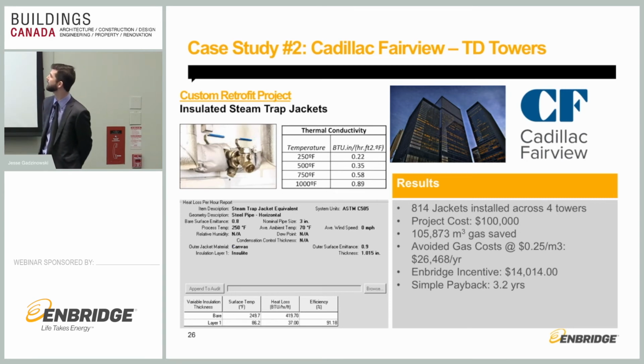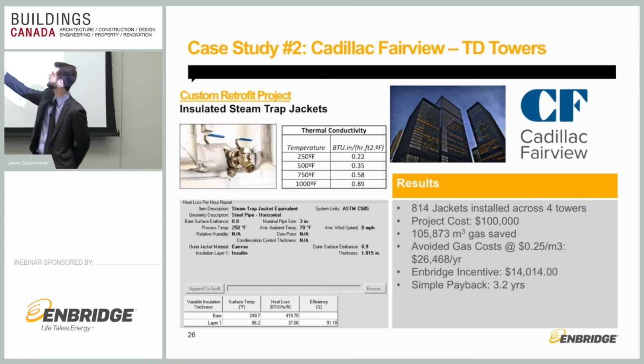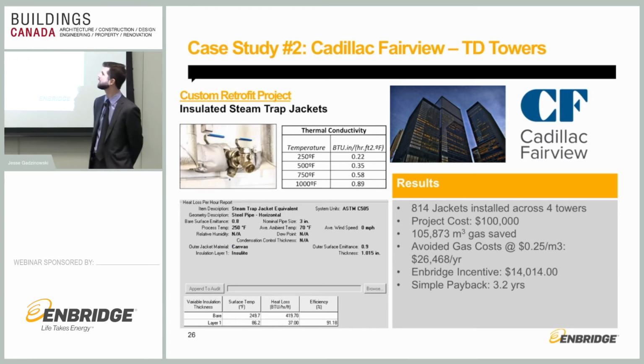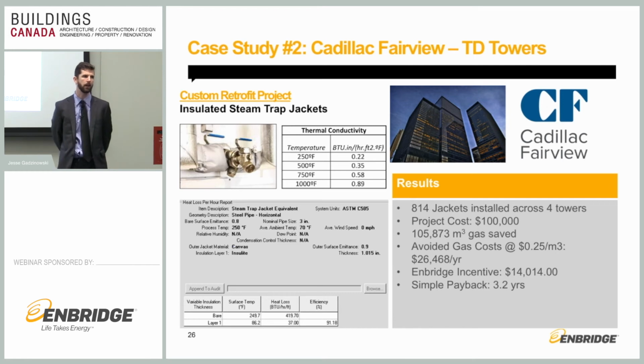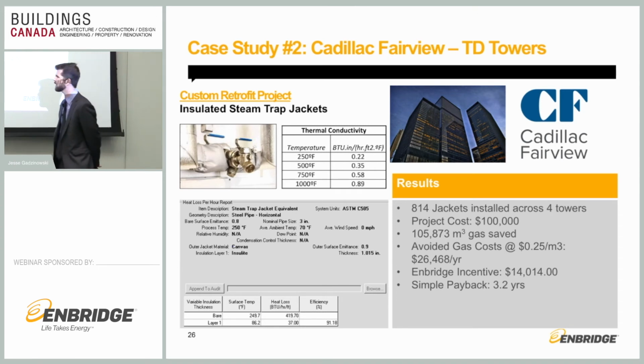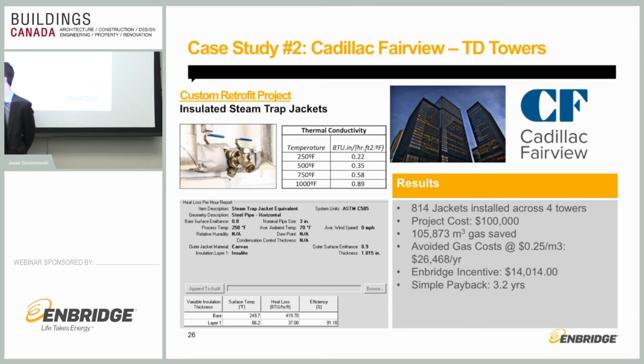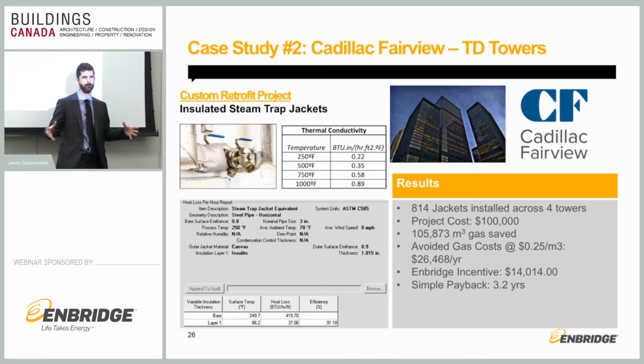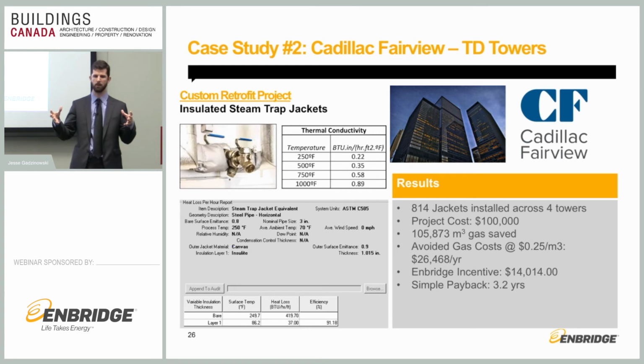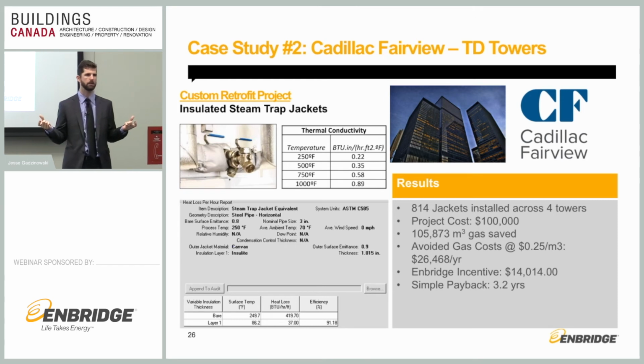It's actually 814. We've got this thermal conductivity chart here, which basically shows the insulation values or properties of the jackets themselves. So you put that into a heat loss calculator here. You can't quite see, but it basically compares the BTUs per hour per foot for a bare steam trap, or we take a steam trap and we say how much surface area is there for that trap. We convert that to an equivalent pipe length and say that's your bare pipe. So you've got 400 BTUs per hour per foot for a bare pipe, and then with the insulation you've got 37 BTUs per hour per foot. So a decent savings per trap.